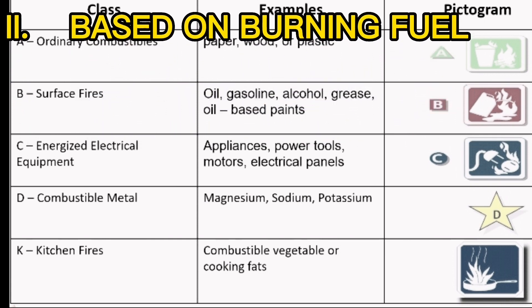Based on burning fuel: Class A — ordinary solid materials such as wood, paper, fabrics, etc. Indicated by deep-seated fire; leaves ashes and embers, glowing coals after burning. Class B — flammable liquids such as gasoline, lube oil, kerosene, paint thinner, etc. Class C — electrical appliances; causes electric shock. Class D — metal fires such as magnesium (a white element burning with dazzling light) and sodium (a silver-white metallic element, etc.); creates violent reaction. Class K — cooking oils and fats.